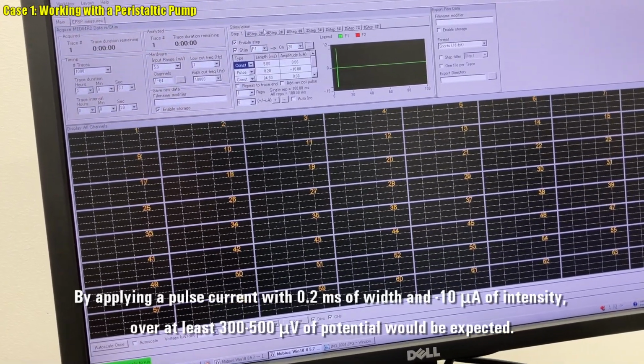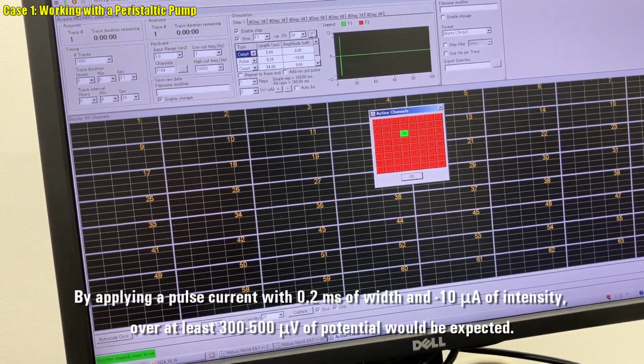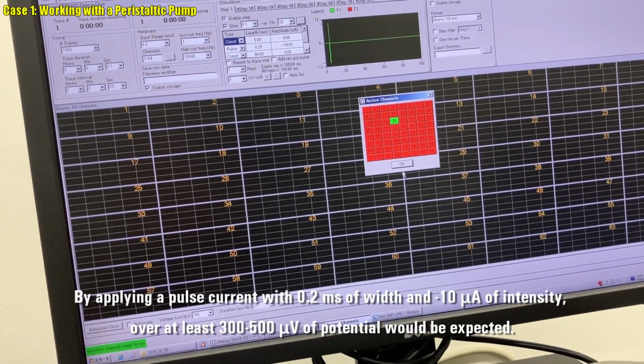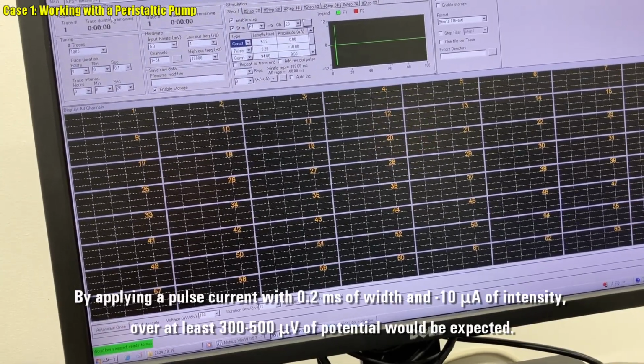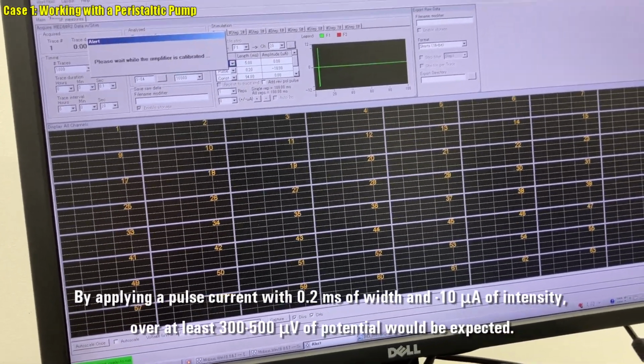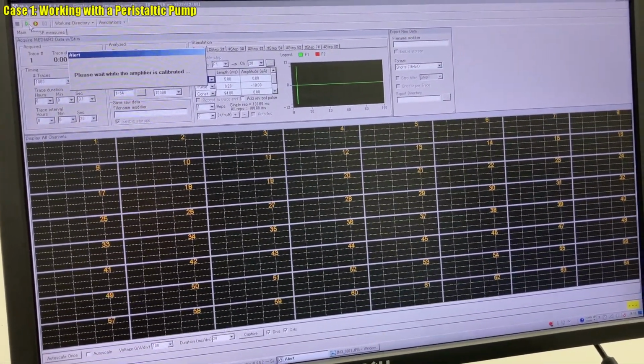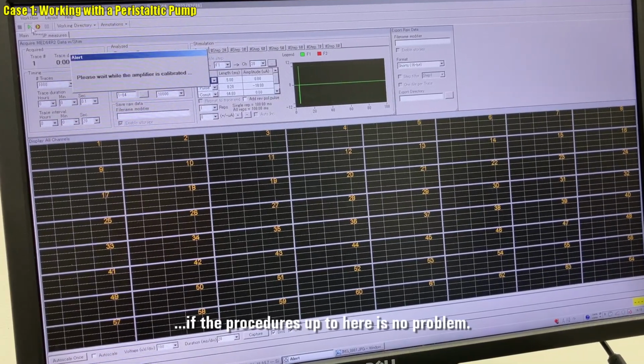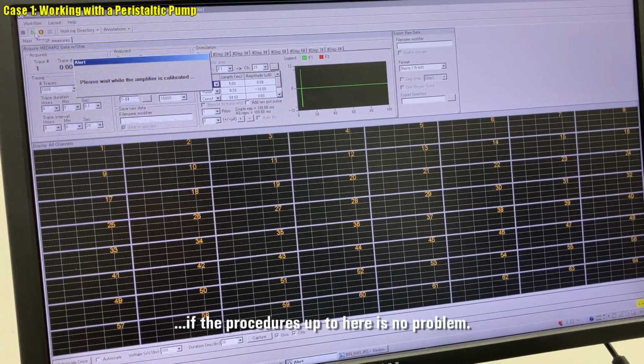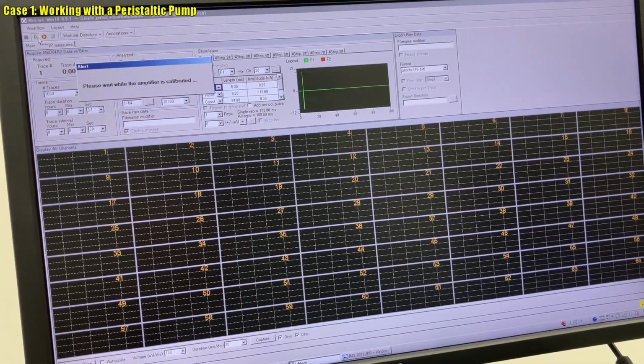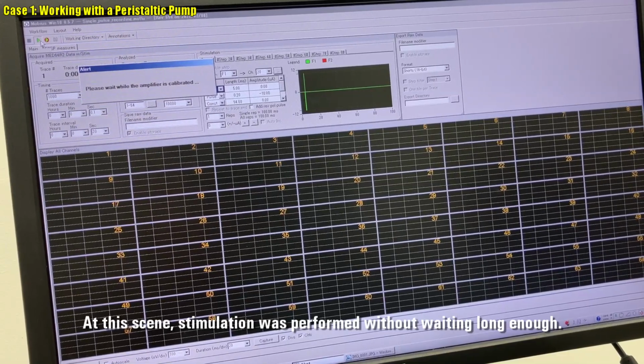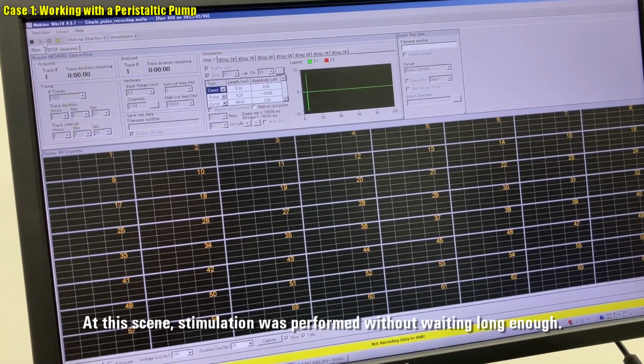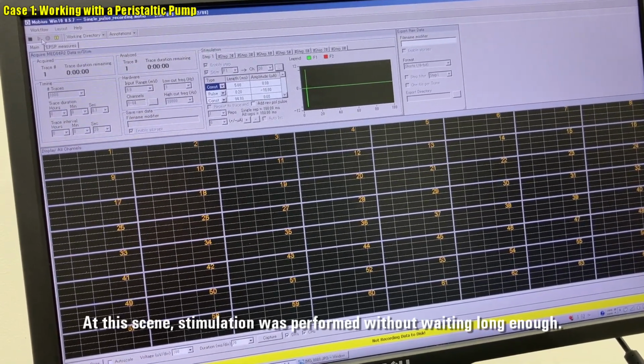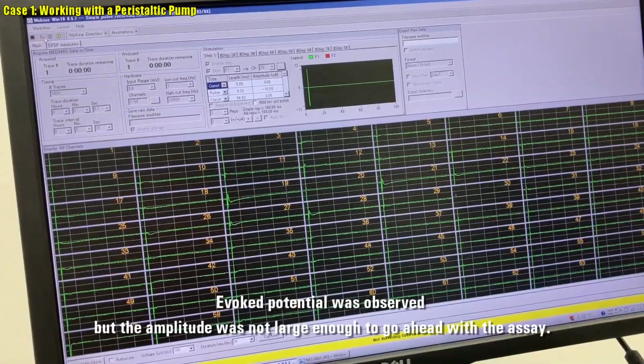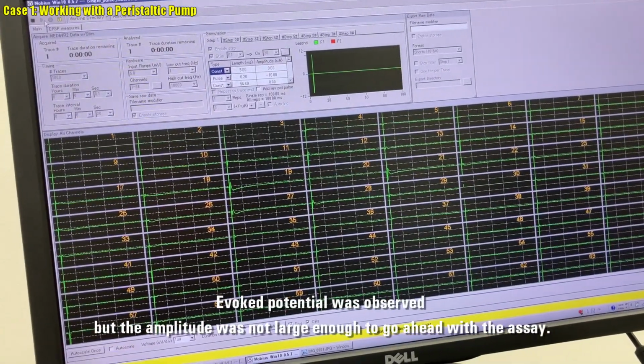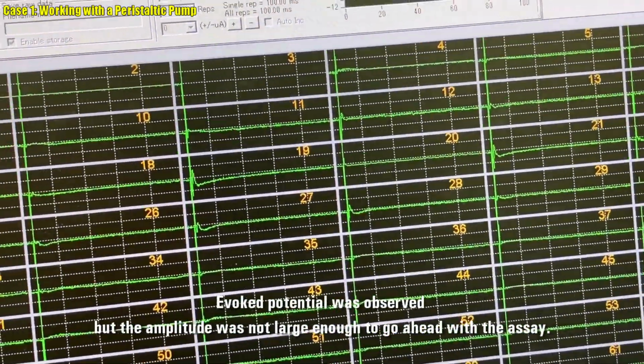By applying a pulse current with 0.2 milliseconds of width and -10 microamperes of intensity, at least 300 to 500 microvolts of potential would be expected, if the procedure up to here is no problem. In this scene, stimulation was performed without waiting long enough. Evoked potential was observed, but the amplitude was not large enough to go ahead with the assay.